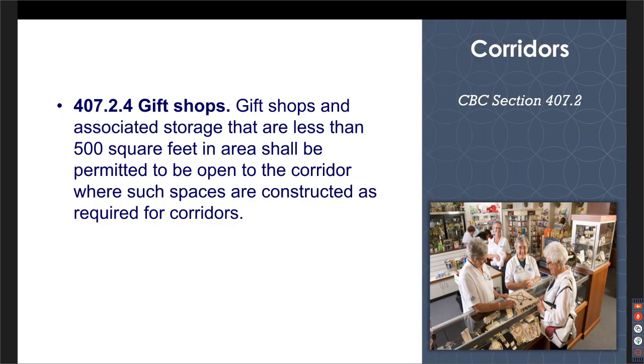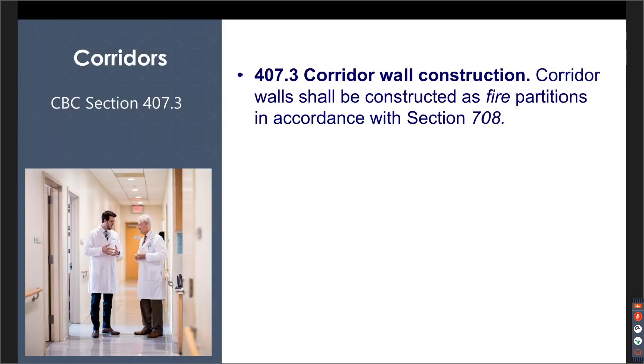Another space that could be open to the corridor with certain restrictions is gift shops. That gift shop and its storage space would have to be 500 square feet or less in order to be open to the corridor. As I mentioned, corridors in California for our I-2s and I-2.1s have to be fire partitions, and they're 1 hour rated fire partitions.